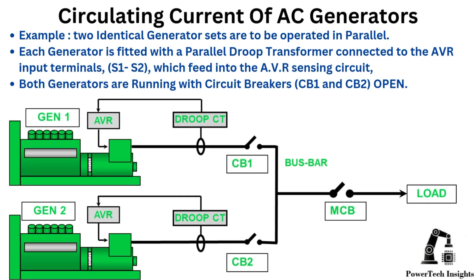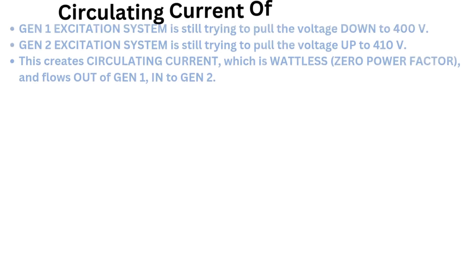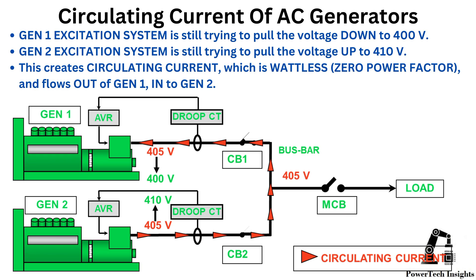Example: Two identical generator sets are to be operated in parallel. Each generator is fitted with a parallel droop transformer (CT) connected to the AVR input terminals S1, S2, which feed into the AVR sensing circuit. Both generators are running with circuit breakers CB1 and CB2 open. Consider the situation where, before closing the breakers, Gen 1 voltage is set at 400 volts and Gen 2 voltage is set at 410 volts. The generators are synchronized and CB1, CB2 are closed. The resultant bus bar voltage will be 405 volts, as the voltages cannot be different when the generators are paralleled. Gen 1's excitation system is still trying to pull the voltage down to 400V, while Gen 2's excitation system is still trying to pull the voltage up to 410V. This creates circulating current — which is wattless, zero power factor — flowing out of Gen 1 and into Gen 2.